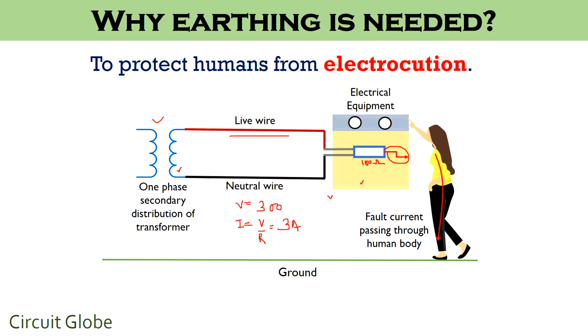Along with the original current which is flowing through the load of the equipment, if at the same time a human touches the outer body of the equipment, that is this metallic part, then simultaneously a fault current will pass through the human body also, resulting in electric shock. Guys, it is generally said that the average resistance of the human body is nearly around 1000 ohms. Although this value is quite larger than the value of the load resistance of this particular equipment.